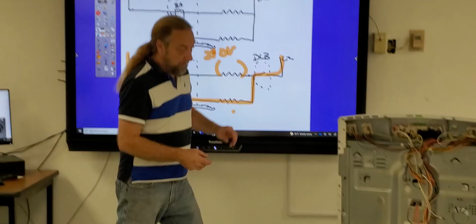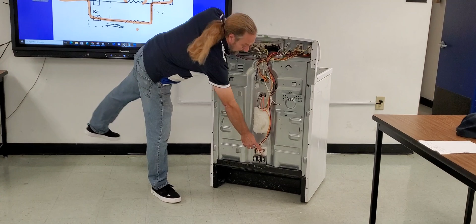When you connect those wires, unplug the machine first, connect the leads, put your meter to voltage, something that's going to read 200 or more. It's usually 300 on the scale of most digital meters. Put it on 300 volts AC, clip the alligator clips here, then plug the machine in and turn it on. Don't do it with your hands on the meters.